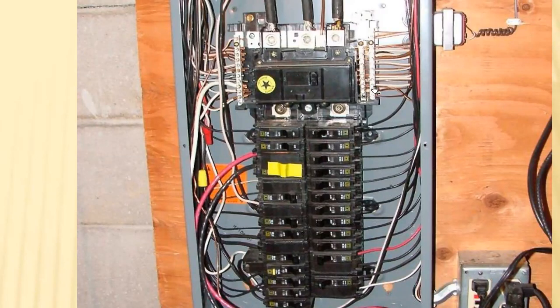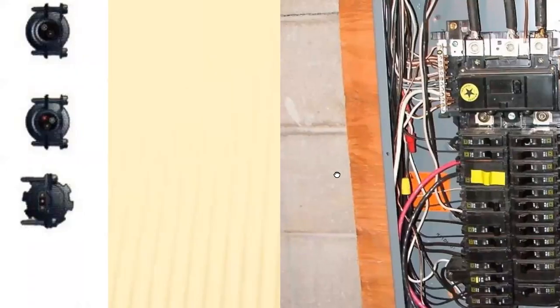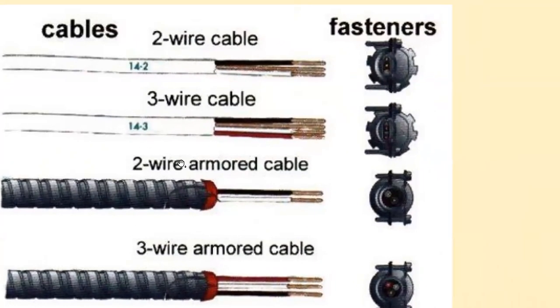grounded. Now from this point, the grounding wire will be connected to receptacles, switches, whatever involves connecting a ground chassis or grounded device box. That is also grounded because electrically, yes, it is connected to the ground, but not directly. It goes to the ground through something else, which is at the same potential, but because there's no single uninterrupted wire that takes you to the true ground, that grounding point of the receptacle is going to be called bonded. We say that it's bonded. So you will hear bonding terminal, bonding screw, bonding wire interchangeably, and I will be doing that on purpose, so you get used to the two words.